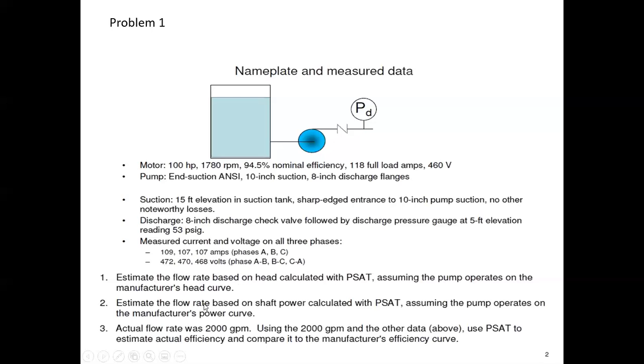Okay, and so we have three different things we're asked to do here. We want to estimate the flow rate based on head calculated with PSAT, assuming the pump operates on the manufacturer's head curve. And we'll have some curves provided to us here. That's part of the homework assignment. After we do that, we want to estimate the flow rate based on shaft power calculated with PSAT, assuming that the pump operates on the manufacturer's power curve. So that's a different curve. We get a calculated power, and we can use that to project the flow rate.